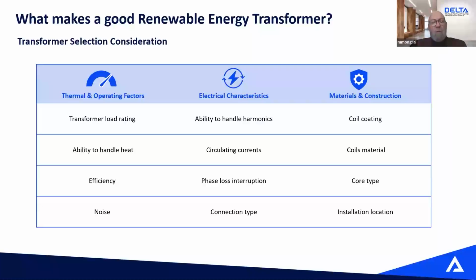So the transformer needs to be able to handle all of that heat. We need a transformer that is very efficient, because the transformer being at the heart of the system, the more losses you have in the transformer, the less energy you can provide to your building or your battery storage. You want something usually that's not going to be too noisy. You need something that is able to handle harmonics. We have solutions that can either handle and or even cancel or treat harmonics.